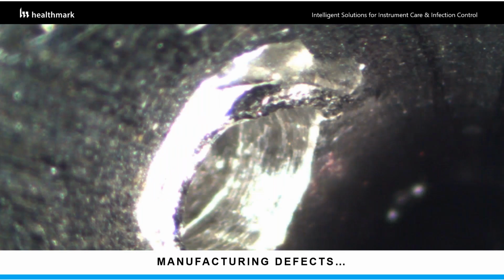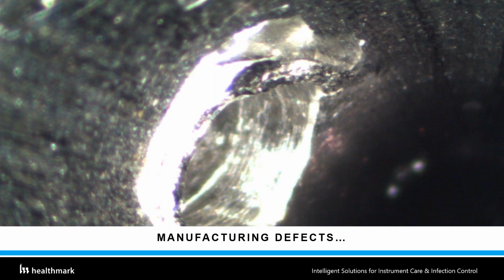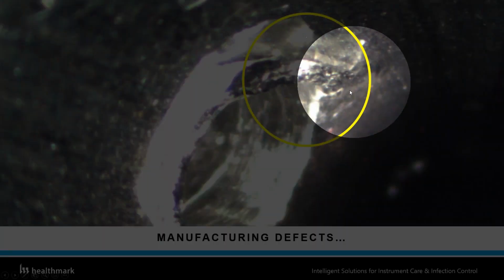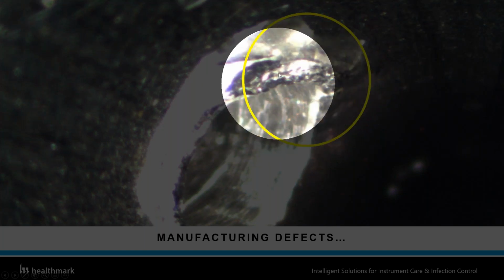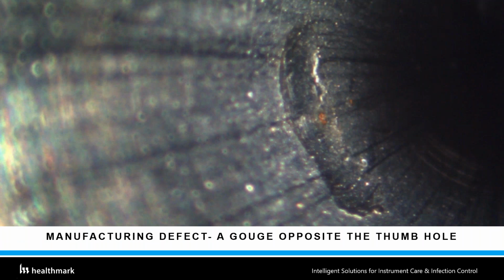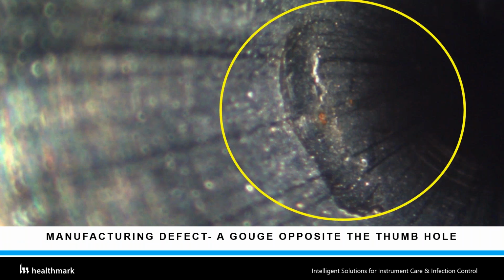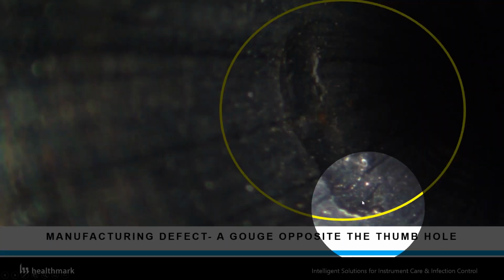Okay, good. Thank you. So why do we have to do that? When I was doing a study for FDA on that arthroscopic shaver, we decided to extend the scope of that and include anything with a lumen, including some of the suction tips and endoscopes. So we purchased a slew of different technologies to look at it. For example, on those thumb holes with the suction tips, you see that when they manufacture these, there's a lot of defects. I think we had about 15 to 20% of them that had issues. We actually had to put them aside and let the manufacturer know. In this one, when they were drilling, the drill went inside.